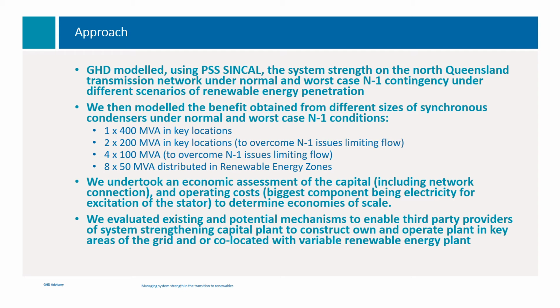We looked at 1 times 400 MVA in key locations, and then 2 times 200 MVA in key locations to overcome N-1 issues, and 4 times 100 MVA again to overcome N-1 issues where you might have a number of outages in the network. And then finally we modelled 8 times 50 MVA distributed in renewable energy zones in a similar manner to what would happen if the proponents of renewable energy schemes were required to install their own synchronous condensers. We also undertook an economic life cycle assessment of the capital and operating costs to determine economies of scale of synchronous condensers.